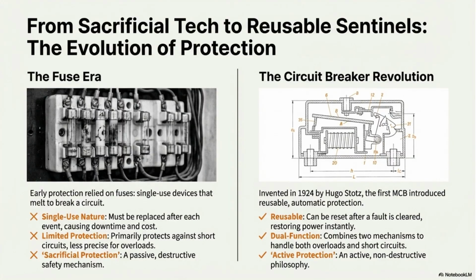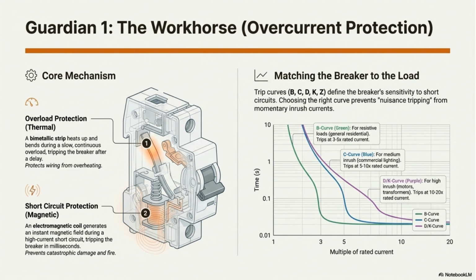Protection has evolved from the sacrificial fuse to the reusable circuit breaker. Fuses were single-use, less precise, and needed replacement. Circuit breakers, invented in 1924, are reusable, dual-function, and offer active, non-destructive protection. Guardian 1, the workhorse, provides overcurrent protection. Thermal protection handles overloads with a bimetallic strip, while magnetic protection handles high-current short circuits instantly. Breakers must be matched to the load using trip curves for effective protection.